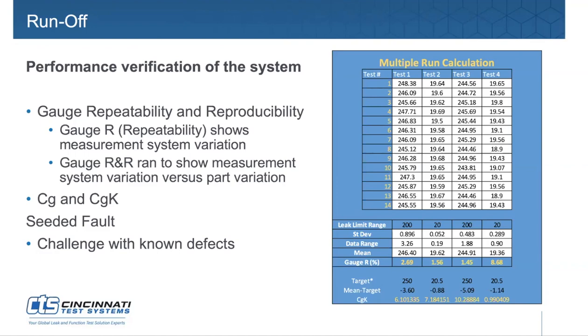Oh, sure. Yeah. So this is a gauge R study, and it's 4 parts. A full gauge R&R study would be 10 parts, 10 times each, 3 operators, and in this case, what we're doing is testing this part over and over and over to see what kind of variation you see test to test, and then comparing it against 4 other parts test to test. And it gives you a good understanding of how well your test cycle time is set up and how well your instrument is measuring a pressure change converted to a leak rate test to test to test.